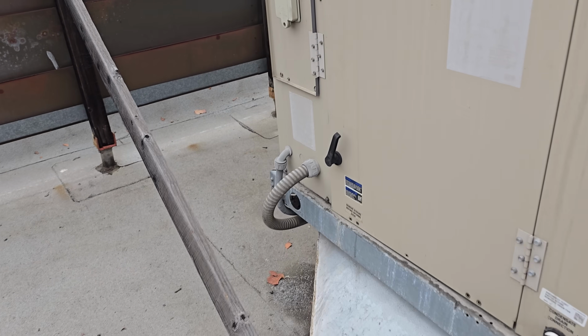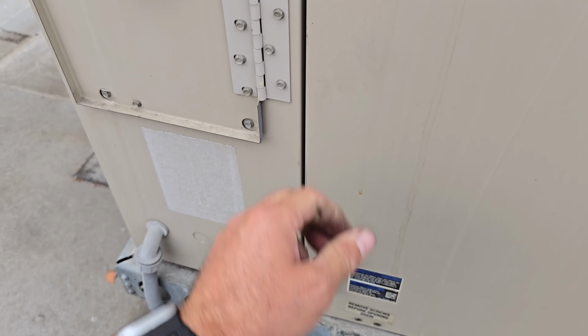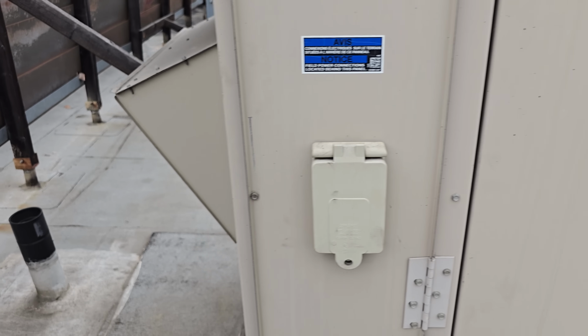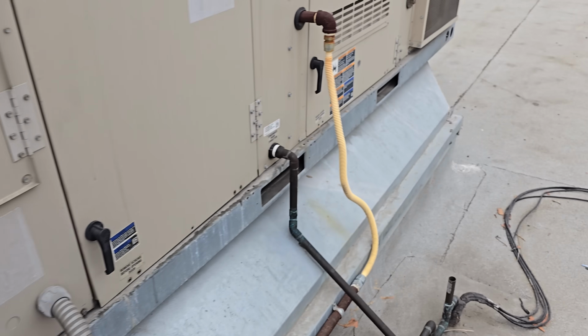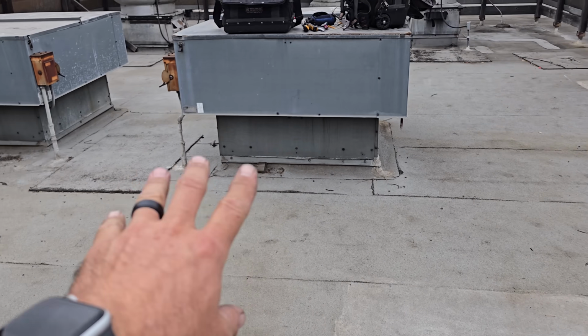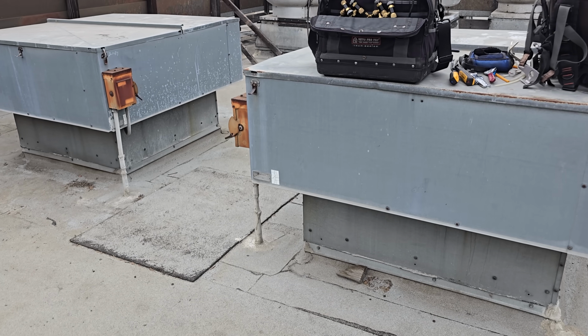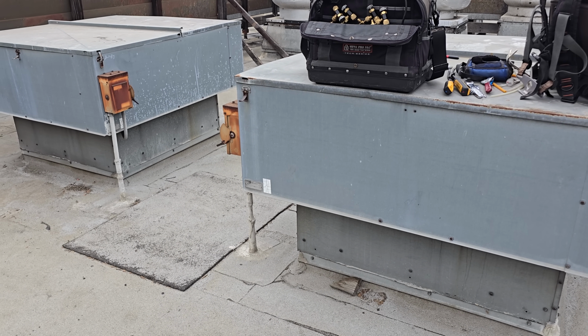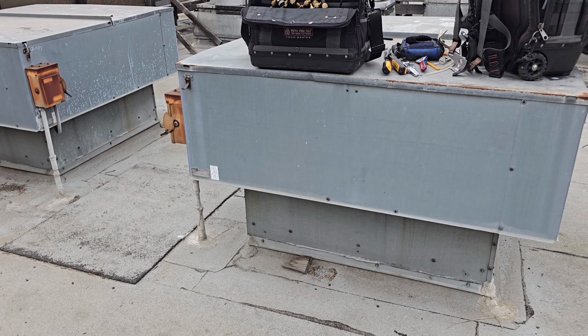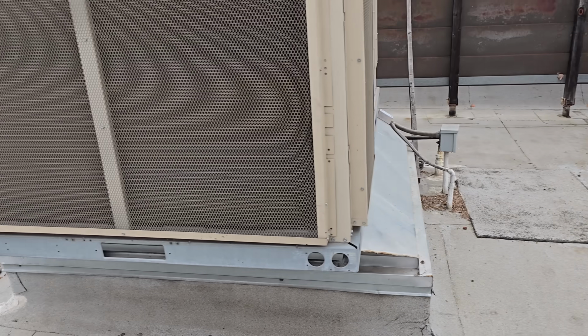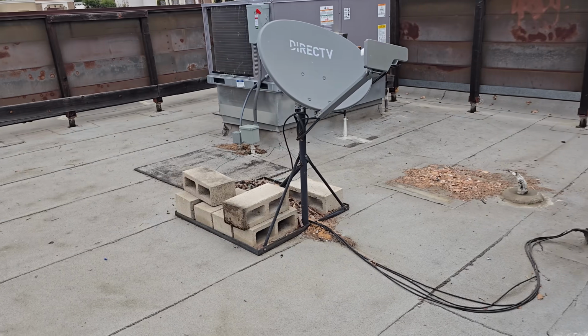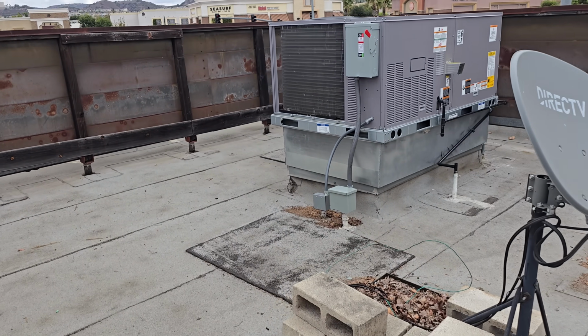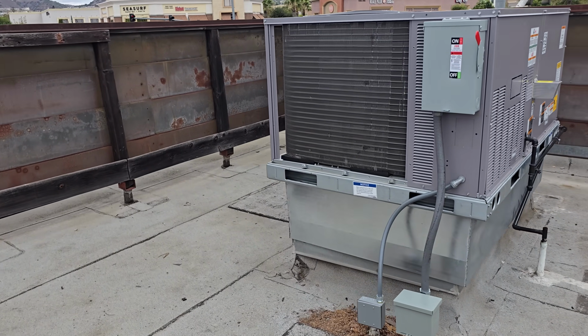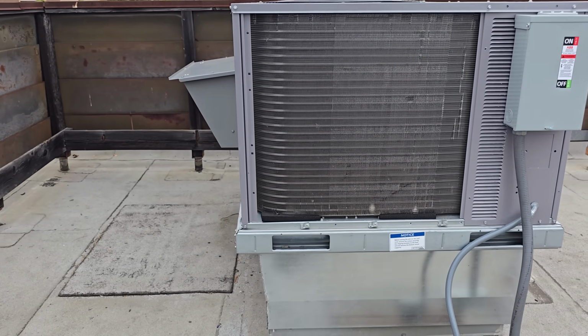We adjusted the outside air dampers a little bit more, but they also need some work because the building balance is extremely negative because both of their makeup units have been off for like 15 years-ish, somewhere in there. So that'll be the next thing, is bringing that up to them, getting the makeup air units working, because then I'll be able to close the outside air dampers on the AC significantly, just open them like 15% on each of them. That way we just satisfy our fresh air requirements for the building.